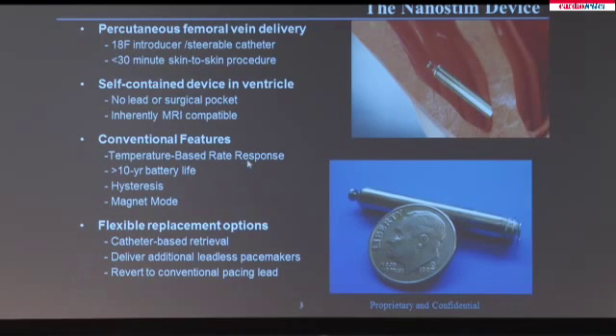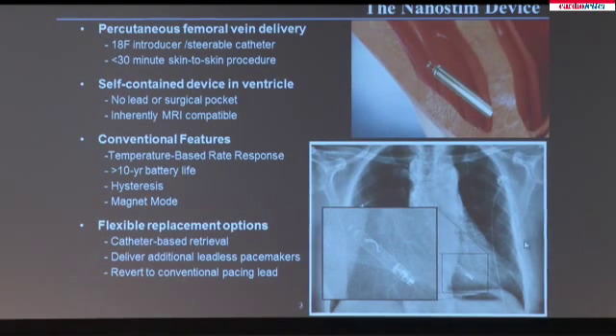It does have some of the conventional features of traditional pacemakers, albeit not all of them. It does have rate responsive capabilities, so as the patient is active, the pacemaker will pace faster to try to accommodate to the higher cardiac output that's necessary. The estimated battery life is over 10 years. Hysteresis and magnet modes, other sort of features that are common to regular pacemakers. And there is also the capability for retrieval. So after the device is implanted, the back end of this device, this little hub, can be captured with a snare, and then the whole device can be unscrewed and removed. And here's just an example of the device in a right ventricle on one of our patients.